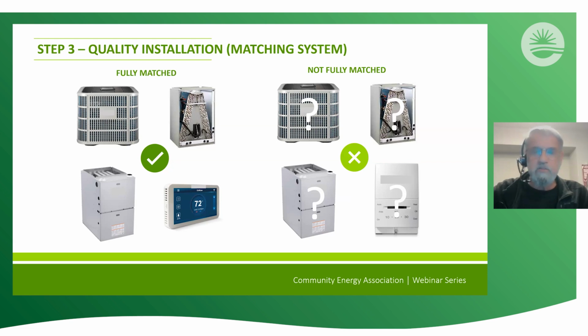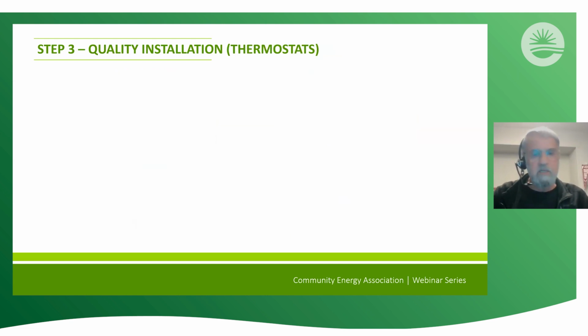You've got three major components to your heating system when it comes to heat pumps. You've got your outdoor unit, your heat pump, say. You've got your indoor unit, which can be a fan coil or a gas furnace. And you've got your indoor refrigerant coil. What you want to ensure is that all those three major components, plus all the associated wiring and controls, are all meant to talk and communicate to each other, because that way they're sharing data, and that way they're optimizing their efficiency and comfort, as opposed to having one brand of outdoor unit with another brand of indoor unit and yet another brand of a coil or a thermostat. You want them all to match. So that's a first step in having a good quality installation.